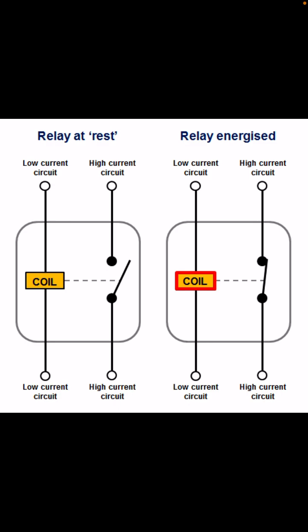A switch, you're manually opening and closing it. But with a relay, the board, usually there's logic involved. So you're just going to have a control board, and that's what's going to provide you with your control voltage. When you get the proper control voltage, like say 24 volts, applied to your low current circuit or the coil, that's going to let your input voltage pass through and go feed to whatever it's supposed to be feeding.